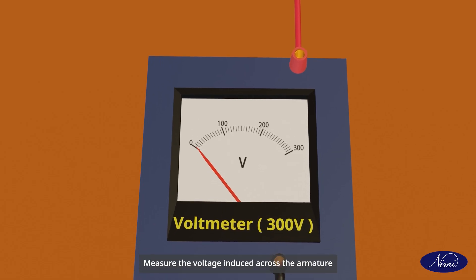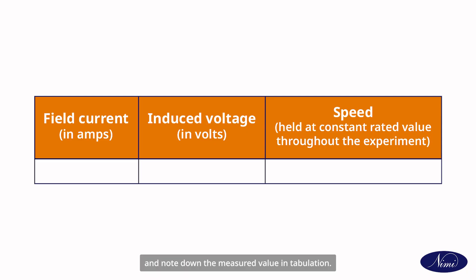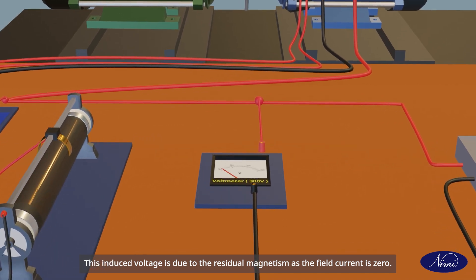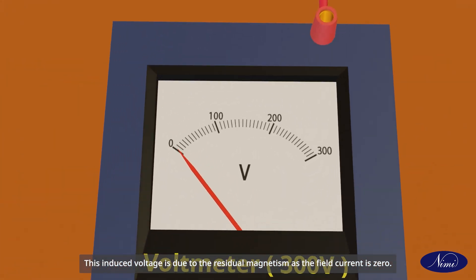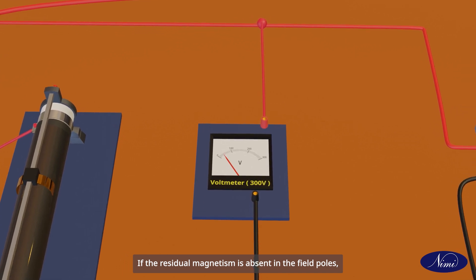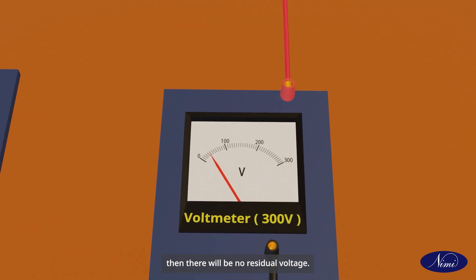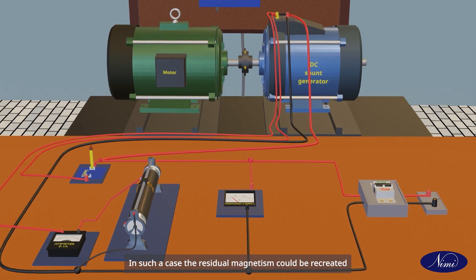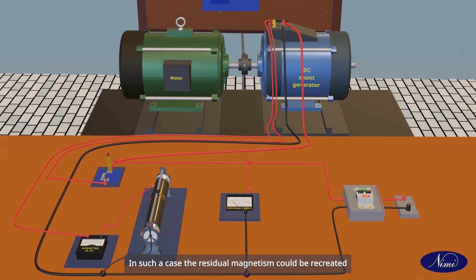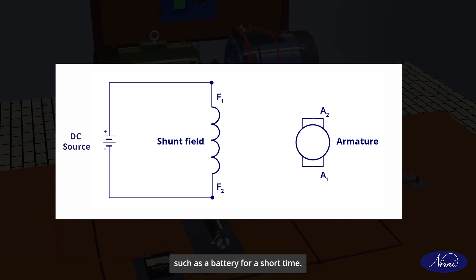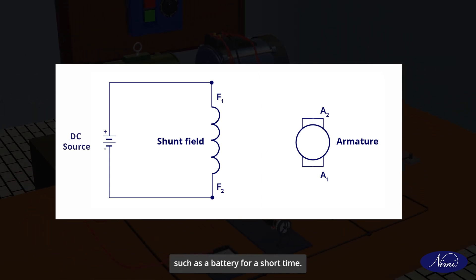Measure the voltage induced across the armature and note down the measured value in tabulation. This induced voltage is due to the residual magnetism, as the field current is zero. If the residual magnetism is absent in the field poles, there will be no residual voltage. In such a case, the residual magnetism could be recreated by connecting the field winding to a DC source, such as a battery, for a short time.